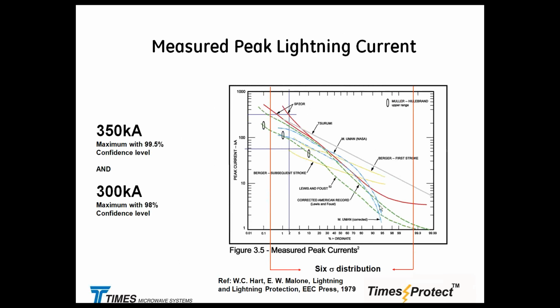Well, what are the typical values right here? Here is a graph. You could do a bell curve if you want to, but what we did right here, here are the percentage of specific lightning current values taking place. So at 50%, basically, you might have currents somewhere from 10 kiloamperes up to 50, 60 kiloamperes in that region. There is a small probability of much higher than that events or values taking place, and there is, of course, distribution on the lower end.